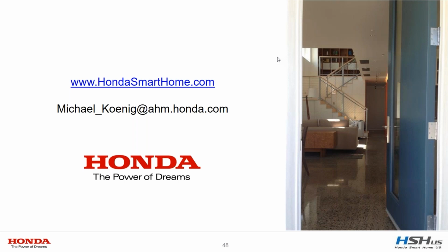That's actually a good question, because it's integral to the heating and cooling design. If we don't pre-cool the house and it's a super hot day, it's going to be hard to keep the temperature down in the house. And so we do have the option for the occupant to turn off the nighttime ventilation and the ventilation in general, just in case that situation arises. The one thing we don't do is we don't do it automatically. We don't have air quality sensors to decide to do it automatically, but the possibility is there. But like I said, if it's super hot, the system just won't be able to keep up. Eventually the house temperature will creep up over several days if it's too smoky to run the fans.